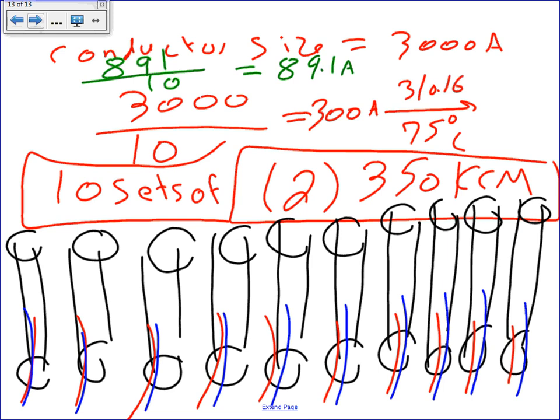So that will give me 89.1 amps. Take it to the same table, guys. Now I know 89.1 is less than 100, but remember, the whole equipment is rated for more than 100. So we go to 75 again. Same table, everything else. What would that under 75 give you? Number 3. Okay? No problem. There's one little problem here. Number 3. Up to this point, if we are not paralleling, no problem.